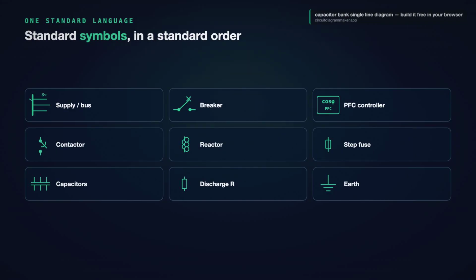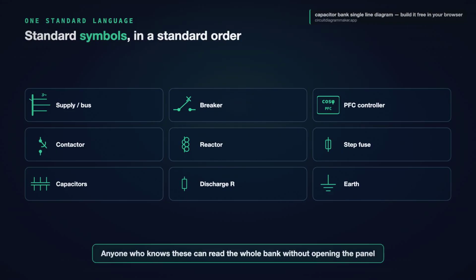A switch with a cross for the breaker. A little box, cosφ, for the PFC controller. A switch with an arc for each step contactor. A coil for the reactor. A fuse for each step. The parallel plate marks for the capacitors. A resistor for the discharge. And earth reaching all of it. That is the whole language of a capacitor bank single line diagram.